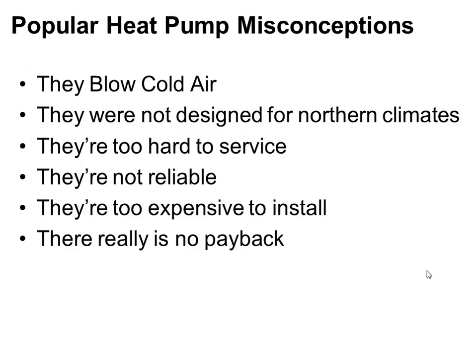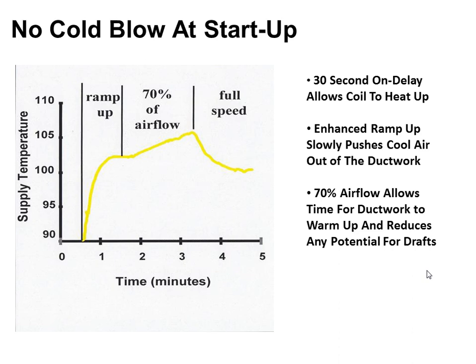So the first one, the cold blow scenario, there's a couple different things we've done to resolve that. The first one is when we start these systems up, we don't immediately blast full airflow when we turn on a call for heating on the heat pump. What we do is we initially turn on the compressor and the heat pump and let refrigerant flow to start warming up that indoor coil, which is the condenser coil. It used to be the evaporator coil, right? So we let that guy start warming up for like a minute or so. Then we start ramping up the indoor blower speed in order to get up to full airflow.